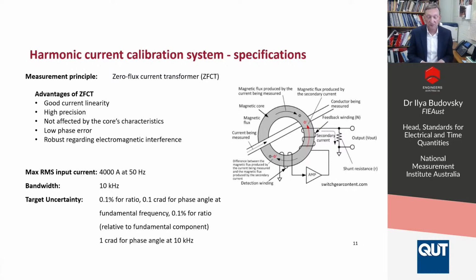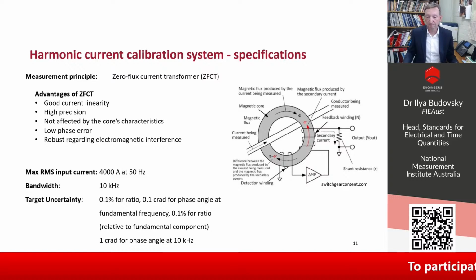The advantages of these systems are that they're wideband, they work on both DC and AC, and they're quite reliable and quite accurate. The disadvantage is that, unlike a Rogowski coil, you can't split the core. You have to put something through the core.